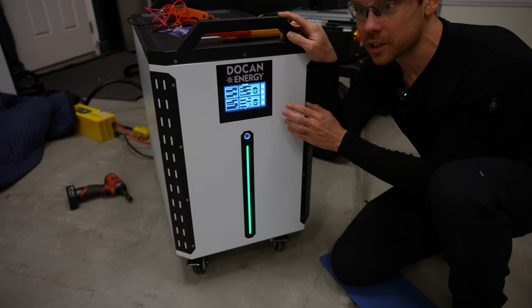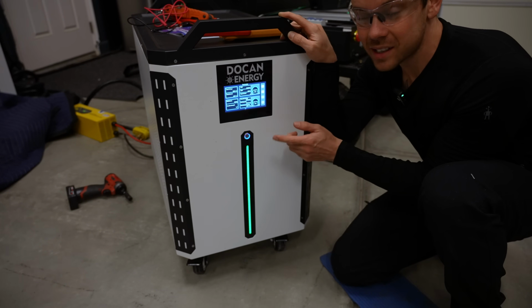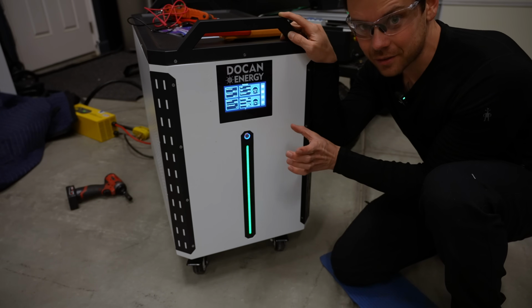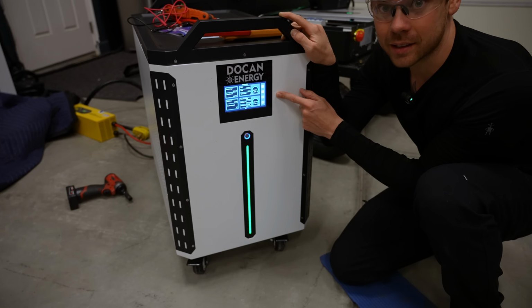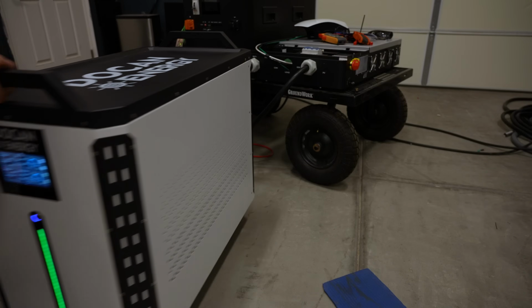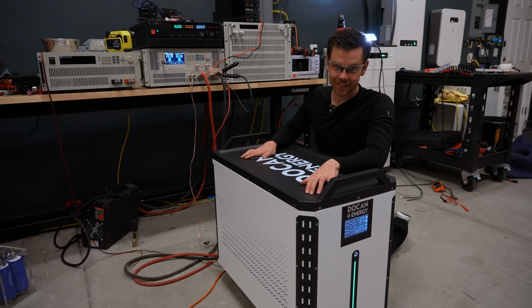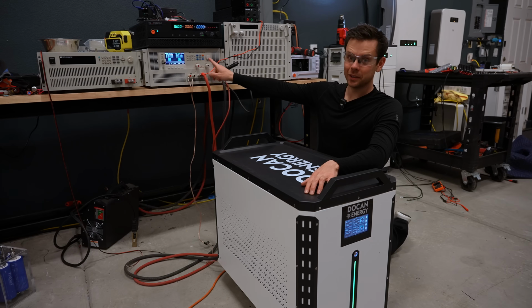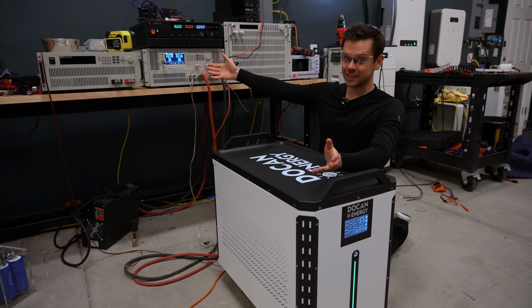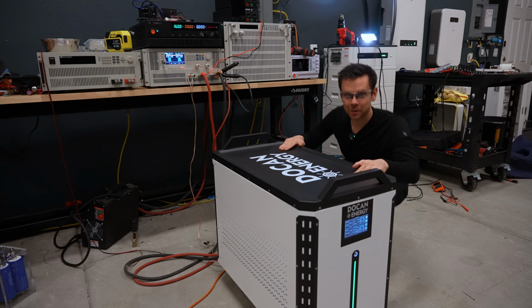So we're going to roll this over to my capacity tester. We're going to see if we can get a disconnect and graph it, and we'll see the true capacity. Now we're going to do a capacity test, and we can almost do a 0.2 C rate. With this machine we can pull 90 amps, so it'll take about 6 hours. We'll come back tomorrow and see what the results are.